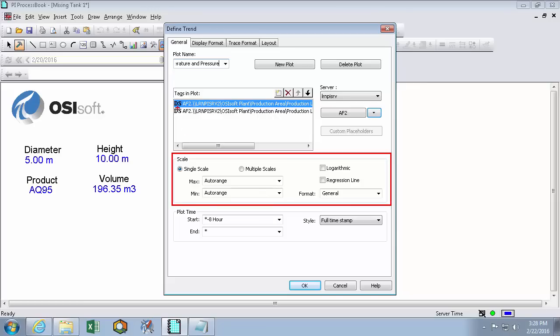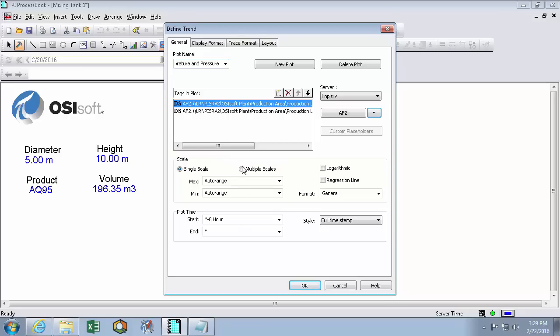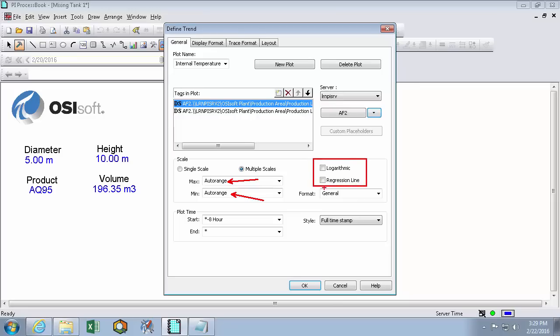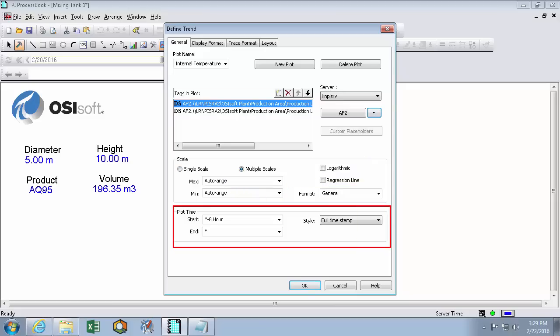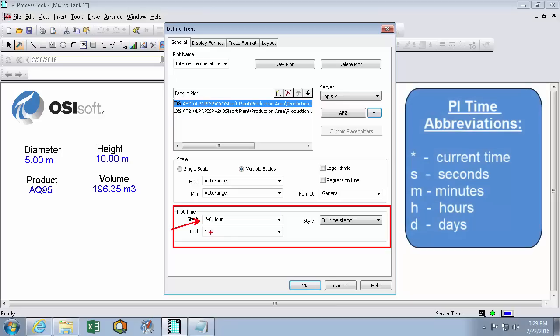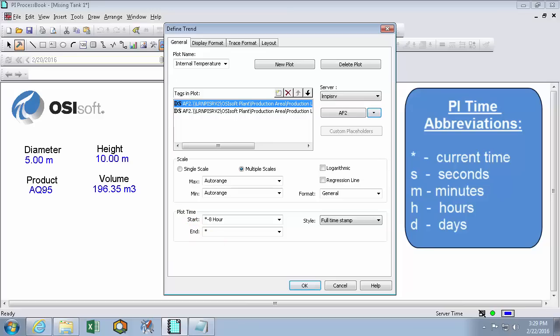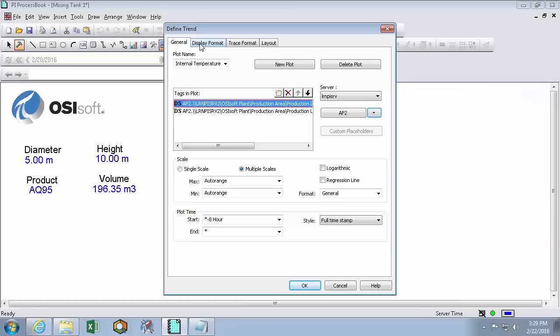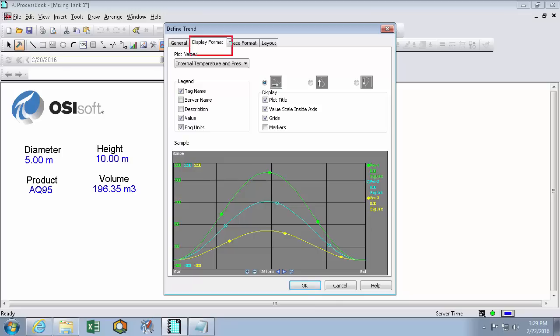And here we get to decide the scale of our trend. So since we have a temperature and a pressure, they're not even the same units. So we'll choose multiple scales. And we'll let ProcessBook autorange the scales rather than defining them manually. And we're not really interested in a logarithmic scale or using a line of best fit. So we'll leave those unchecked. And here we decide how wide our trend should be. So I think 8 hours between 8 hours ago and the current time is appropriate.